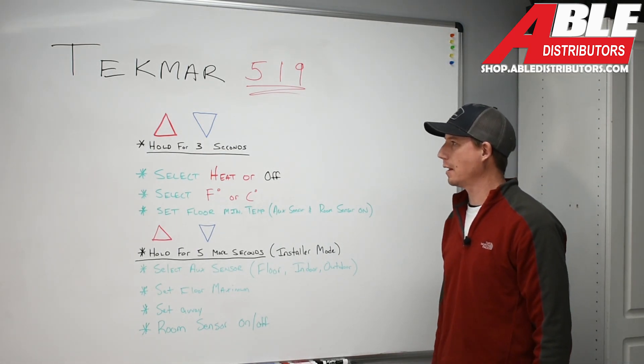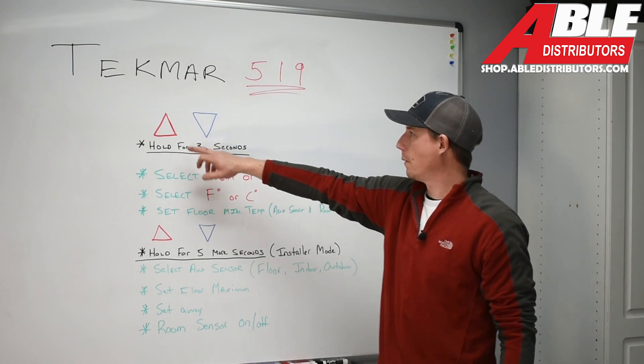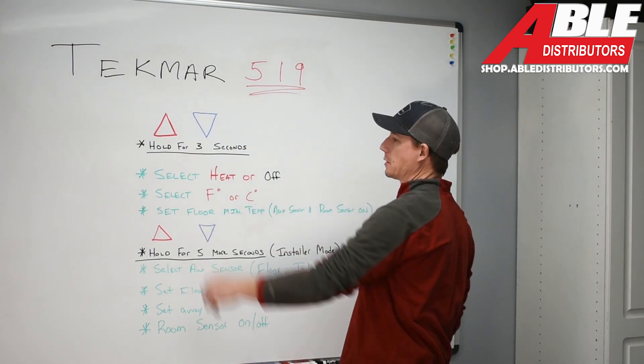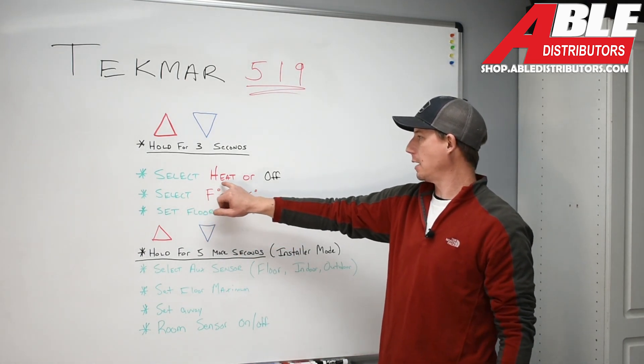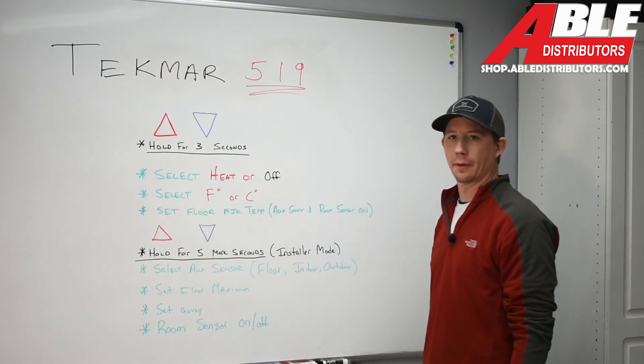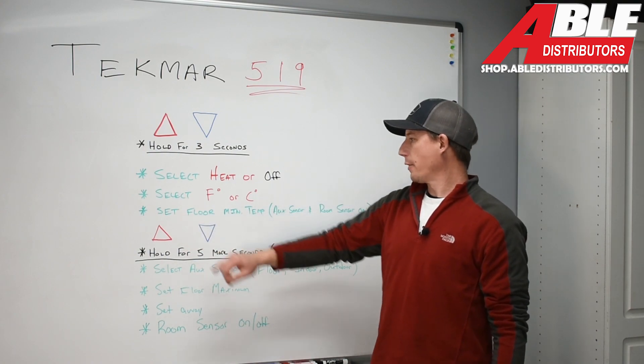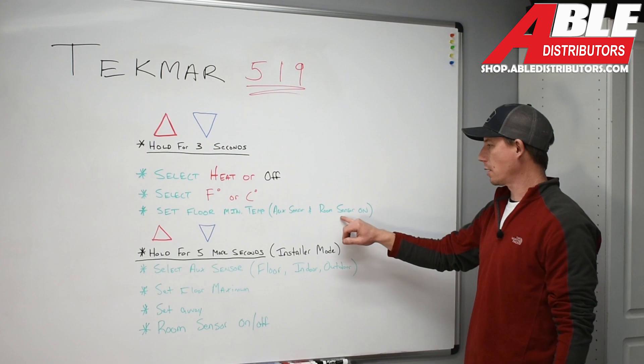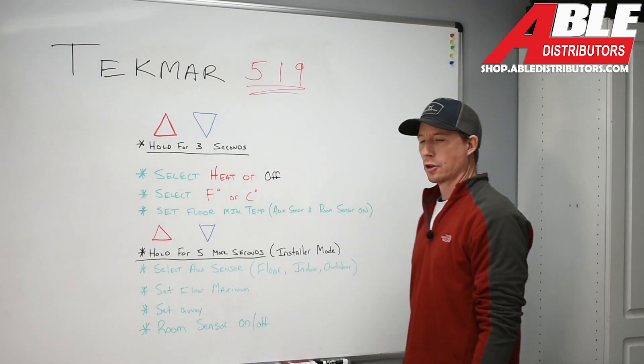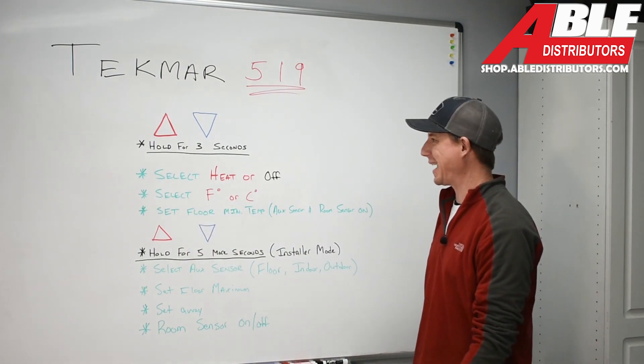Back at the Tekmar 519 controls — we're going to get into the button section and how to select desired parameters. We have two buttons: up and down. To access the homeowner section, hold both buttons down for three seconds. That allows you to select heat on or off. Moving down one step further, you can select your desired temperature reading in Fahrenheit or Celsius. You can also set the floor minimum temperature, but an auxiliary sensor and a room sensor must both be present.